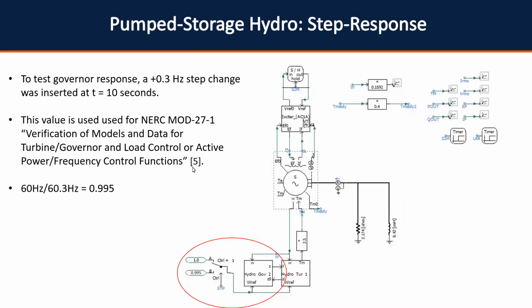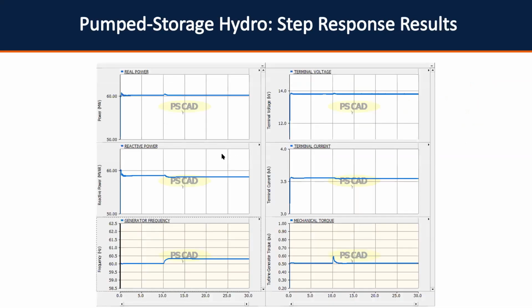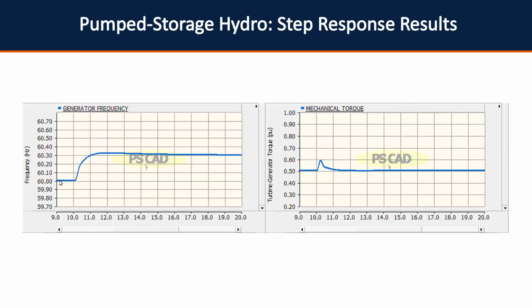So what I wanted to do was test the governor response. I introduced a 0.3 hertz step change into the governor. That's what I've seen used when we do governor testing for NERC MOD-027. So at 10 seconds, I introduce a 0.3 hertz step change, and this is the response. We get a little bump in real power, a drop in reactive power, a drop in current, which makes sense, and terminal voltage. Generator frequency comes up to 60.3, which it does steady out on.